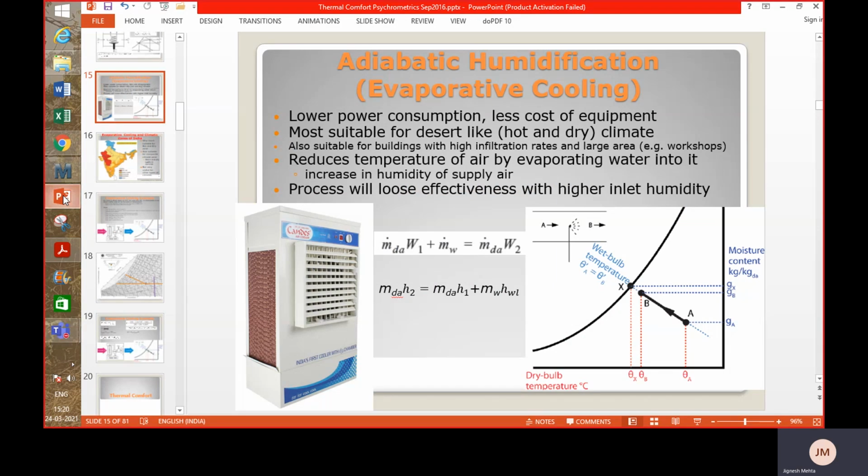The purpose of this lecture is to explain the psychrometric process of adiabatic humidification. The same was explained with the help of the device called an air washer, where you create sprays of water and air passes over that. Now, if this water is simply recirculated, it is neither cooled nor heated, then the water temperature reaches the wet bulb temperature, and if there is 100% effectiveness of the process, then the air would also reach the wet bulb temperature.